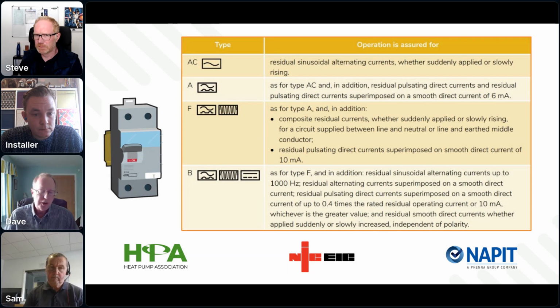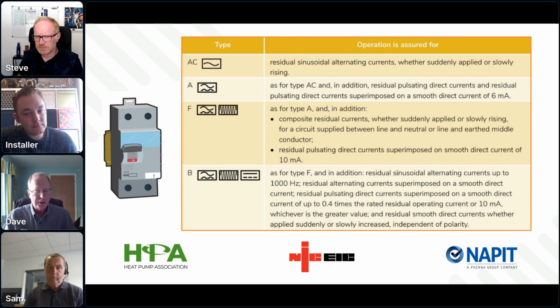That leaves you with thinking about Type F and Type B, and it's strange that it's not in alphabetical order, but B is kind of spec'd above F. The question I would ask myself is, can I guarantee that the characteristics that the RCD is exposed to will result in the effective operation of a Type F? If I can, then a Type F is probably fine. If I can't, then I should go for Type B.